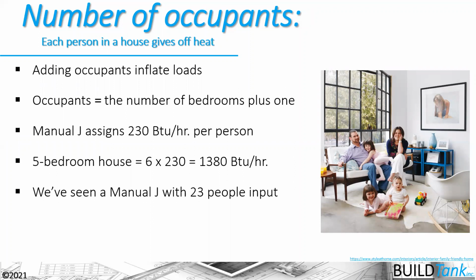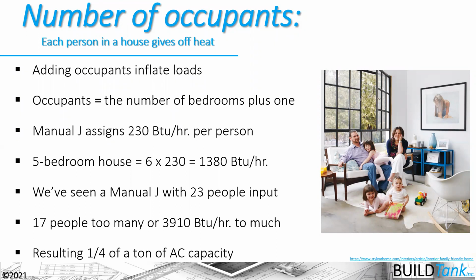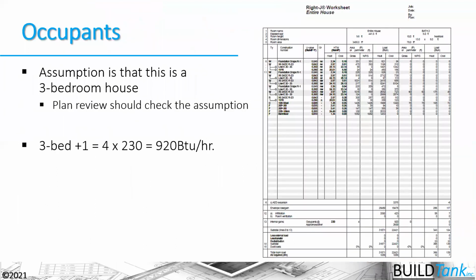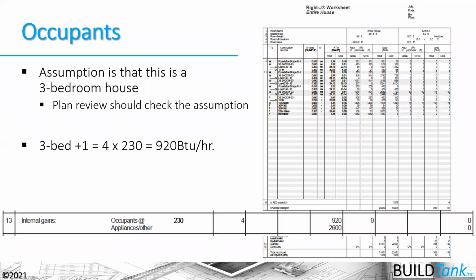Now, we've seen some gross manipulations. In this case, 23 people were added to the house. That's a huge load. That's about 1/4 of a ton of additional air conditioning capacity that the house actually didn't need, which might mean that the AC system is short cycling, or that the coil is freezing. There are a variety of different reasons why oversizing of the equipment shouldn't happen in our houses. You can look at these worksheets that come out of the Manual J, and you can see where the loads are being entered. In this case, this 3-bedroom house has been entered with 4 occupants, and you can see that it was done correctly here.